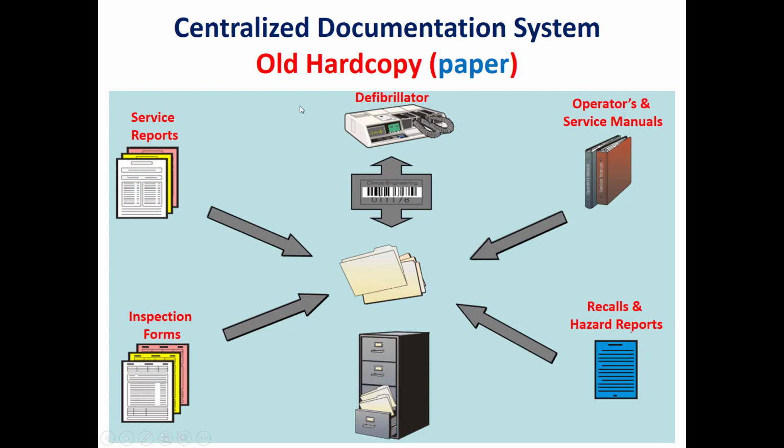Also, another example will clarify this point. Each medical device has a lot of documents or files related to it. Some of these files are the service reports, which relate to corrective maintenance. Some are the inspection forms, related to the IPM or preventive maintenance. Some of these documents are the operational and service manuals of this specific device, and some are related to recalls and hazard reports. So we have a lot of files and documents for each device.